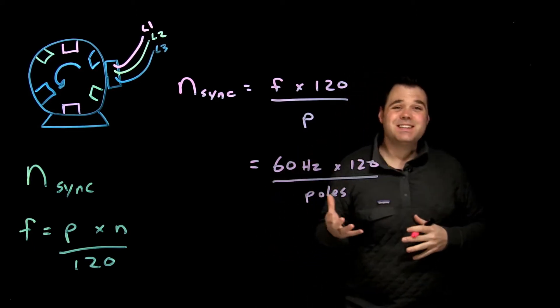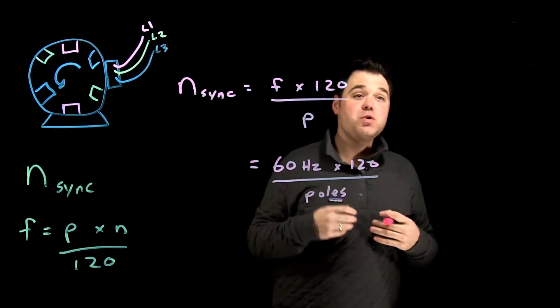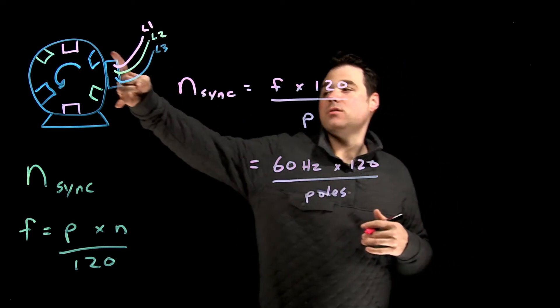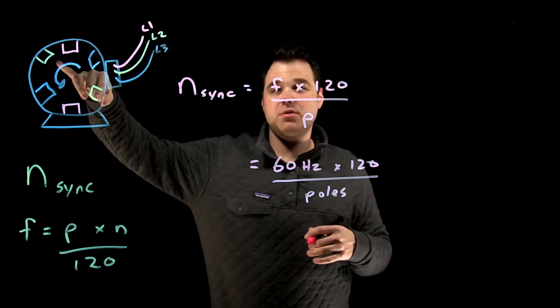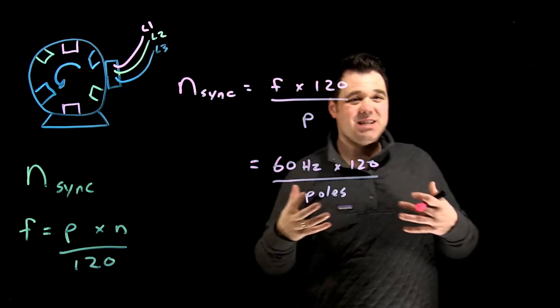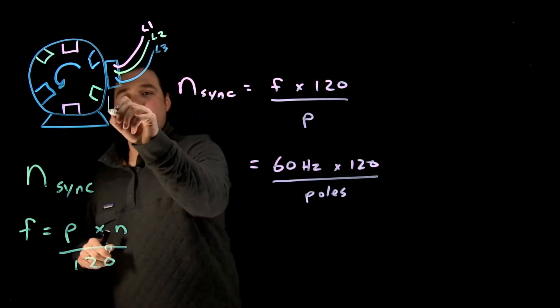Now this is the number of individual poles. So in this motor here, I'm a two pole motor, so I have two poles per phase—two poles for the A phase, two poles for the B phase, and two poles for the C phase. And that of course is most likely going to be stamped right on the nameplate.